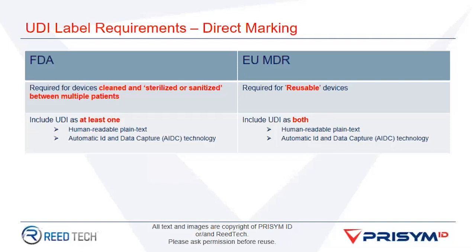Must the quantity be included on an MDR compliant label? I believe quantity is one of those fields that needs to be there. It's currently one of the fields that I'm aware of on the FDA's labels. So quantity of the package, to my best understanding, would need to be included.